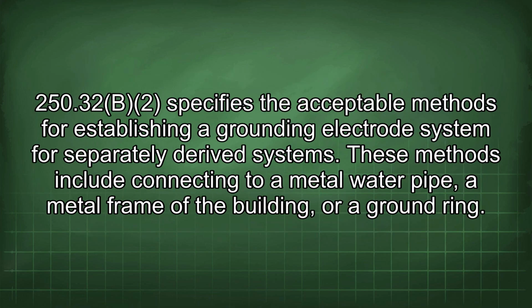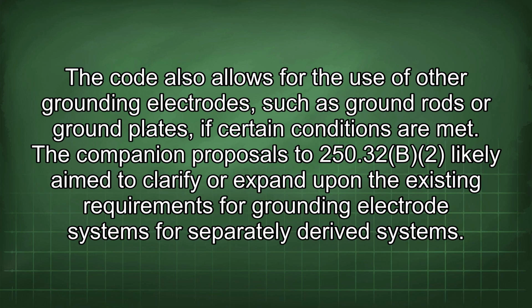250.32(B)(2) specifies the acceptable methods for establishing a grounding electrode system for separately derived systems. These methods include connecting to a metal water pipe, a metal frame of the building, or a ground ring. The code also allows for the use of other grounding electrodes, such as ground rods or ground plates, if certain conditions are met.